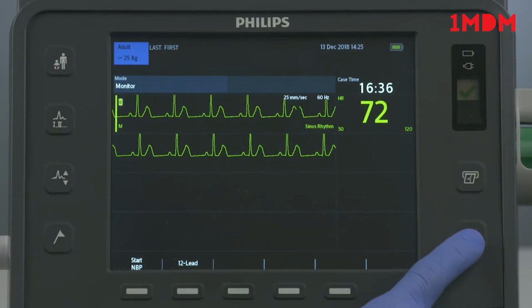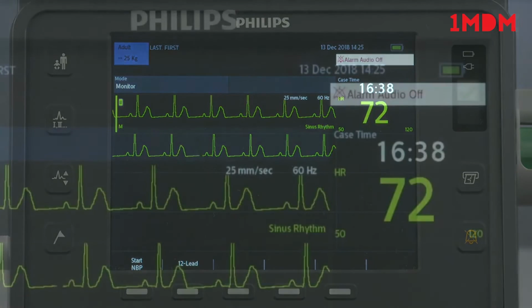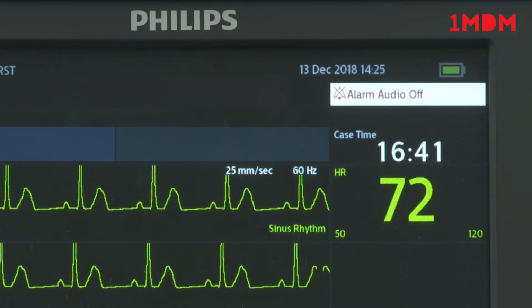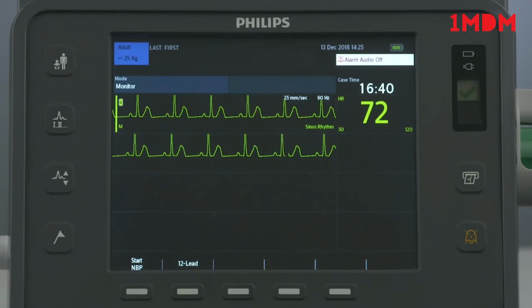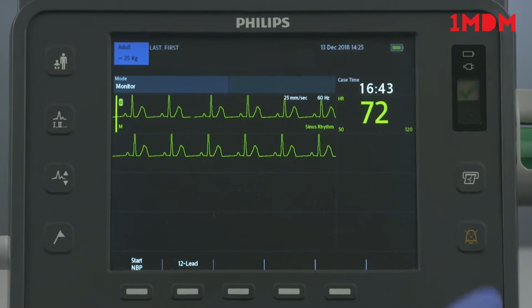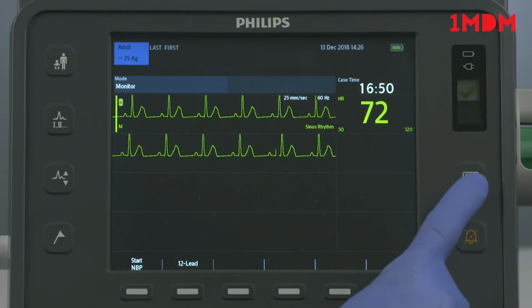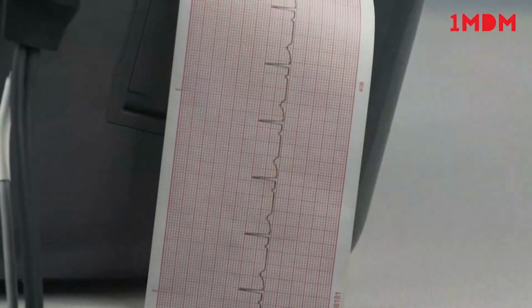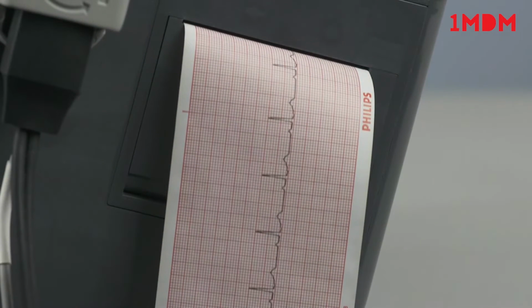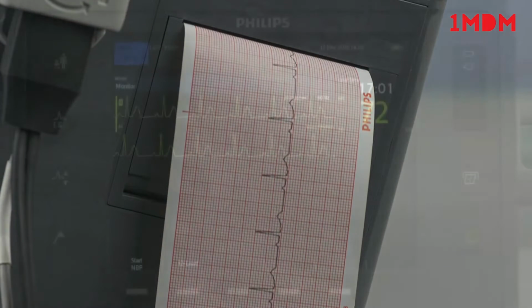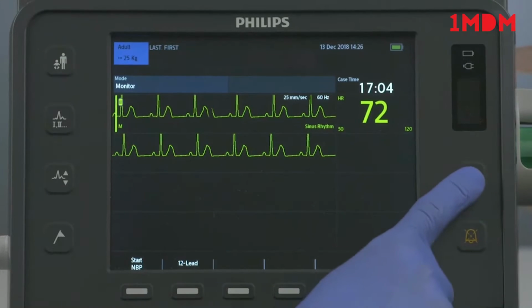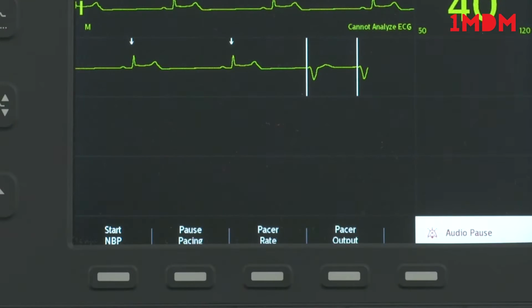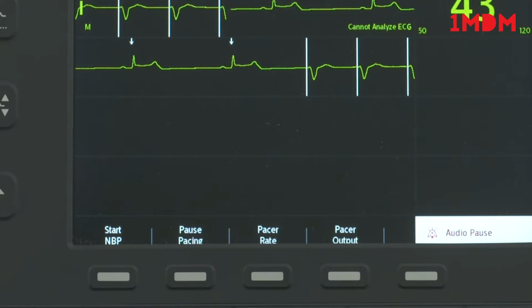This is the Alarms button. It pauses all audible physiological and technical alarms for the configured time interval. Pressing it during the pause interval returns alarms to their previous settings. Press the Print button for a continuous printout of the primary ECG and other selected waves with event annotations and measurements. Press the Print button again to stop printing. Below the display, there are 5 soft key buttons that perform the function listed on the soft key label immediately above. The button labels change according to the function you are performing.